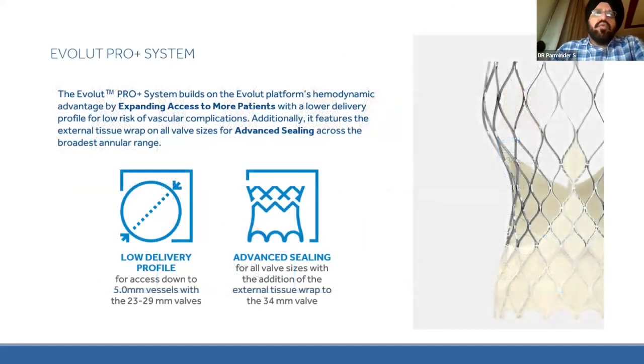Evolut Pro Plus has two features in addition to the previous Evolut Pro valve. It is a low profile delivery system which just requires 5mm vessels for 23 to 29mm valve. And for 34mm valve, it requires 6mm. And there is a sealing skirt which is available on all the valves in addition to the 34mm valve. So this protects against PVL and has a good delivery system which can easily go through a 14 French sheath.